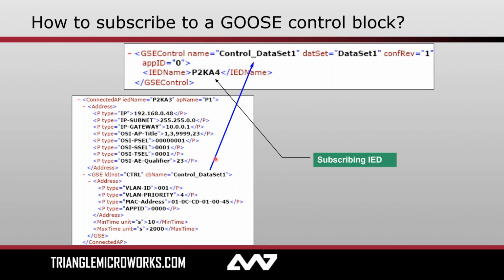This first larger one here is from the communication section of the SCD file. If you remember from last time, this is near the top of the SCD file or all SCL files and contains the communications settings for all the different devices in my substation. So here we're looking at the communication settings for one particular IED. Up at the top, we have maybe the more MMS level, the TCP/IP stuff like the IP address and gateway and subnet mask. But then down here, we have relevant GOOSE settings.